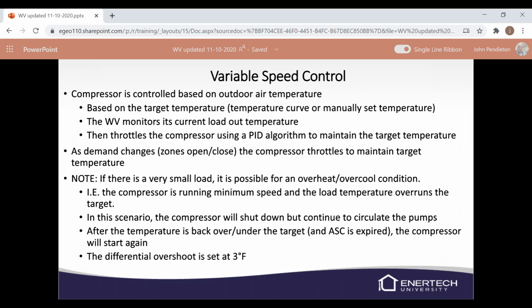Variable speed control. The compressor is controlled based on outdoor air temperature, and there's a target temperature for the compressor as well, so the temperature curve or the manually set. The unit monitors the current load out temperature, and then it will throttle the compressor based on an algorithm in the controls to maintain that target temperature. When you look at the screen, it's showing your pumps, your temperature differences, and your actual supply temperature and your target supply temperature. That target supply temperature is looking at outdoor temperature and the speeds and temperature difference, and it says, okay, this is what I should be at. This is what I'm going to try to get to. As the demand changes, so zones open or close, the compressor will throttle and maintain your target temperature.